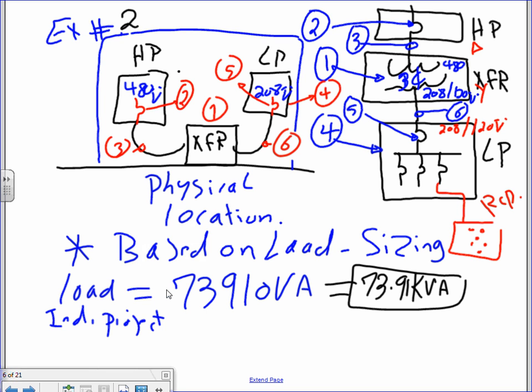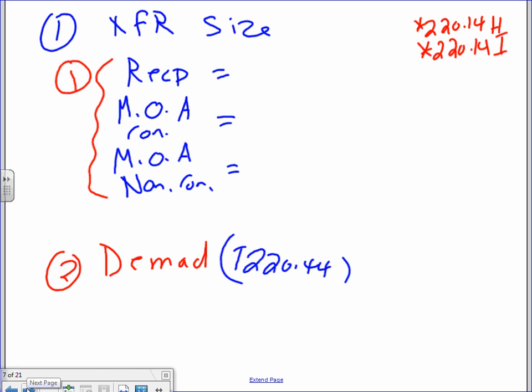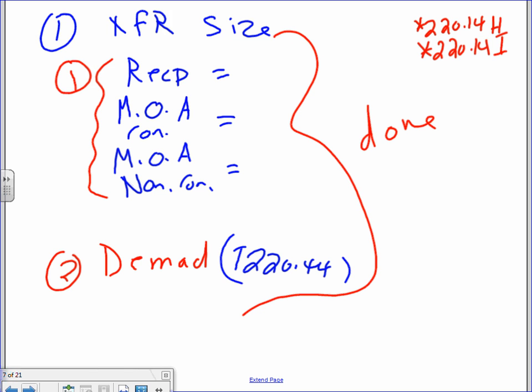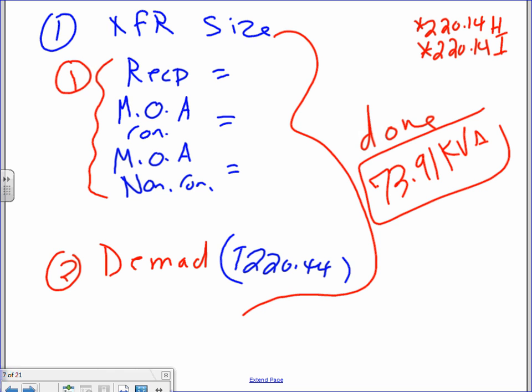So I have 73.91 kVA, right? So that's my kVA. Now I need to go size an overcurrent protection device. Now, Adam, all this calculation and the demand, can you guys put something like this? All this done. And the size was, what was it again? Matt, remind me. 73.91 kVA. Can you guys just put right next to that one, all this calc, done.